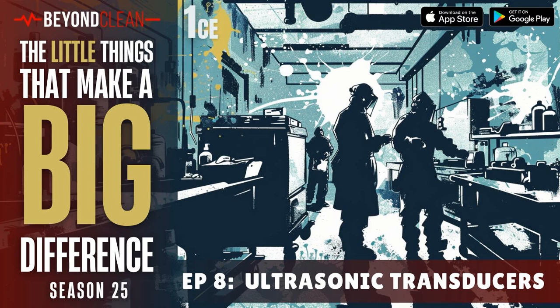So you have to have a different means of delivering that mechanical cleaning power into those elements, and that's when ultrasonics come into play, because those bubbles are formed within the entire volume of the fluid that you submerge your instruments in. And if you push the liquid through the instruments, or you allow the liquid to fill the instruments as well, they are created inside as well, which is exactly what we are talking about. Right. So you can really get in there on those instruments.